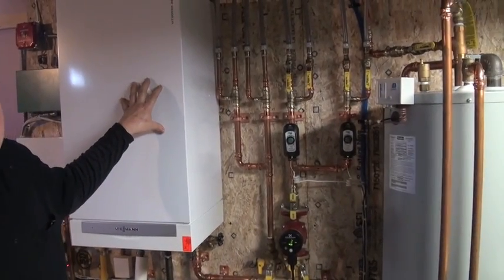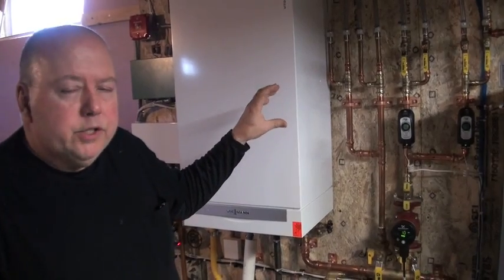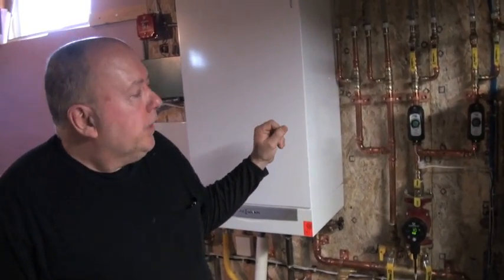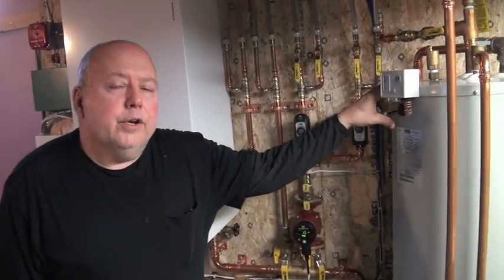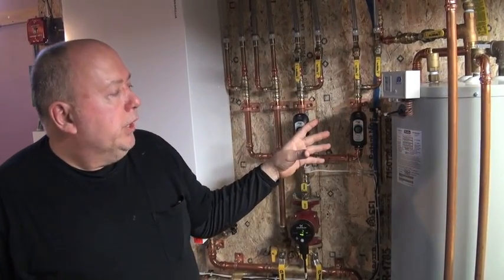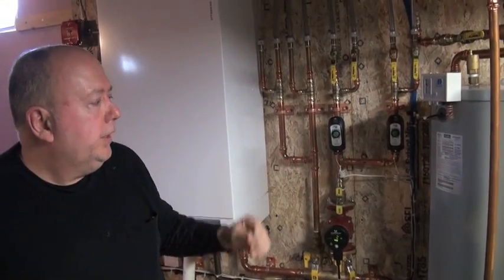Based on the minimum output of the boiler, which is approximately 25,000 BTU, in our low-temp heat zones using heating edge baseboard, we would have created a short cycle situation. So to eliminate that possibility, we've gone with the Turbomax T33, which is a 36-gallon, three-coil domestic tank. We're utilizing it for the domestic demand as well as the buffer tank considerations.